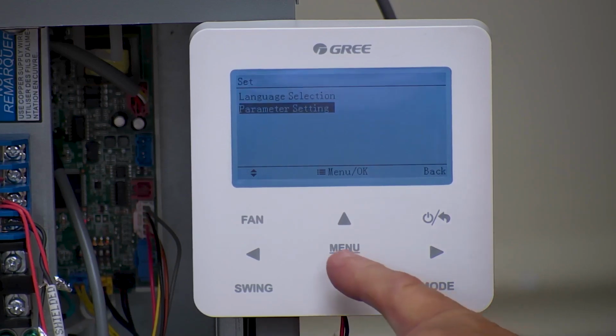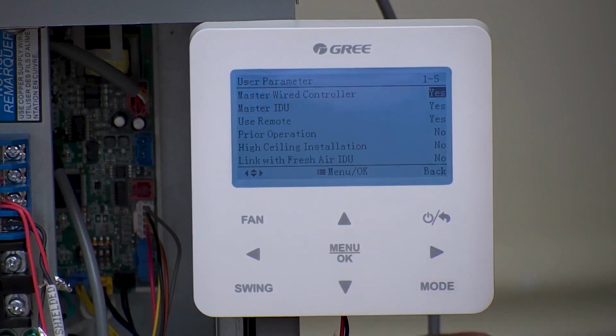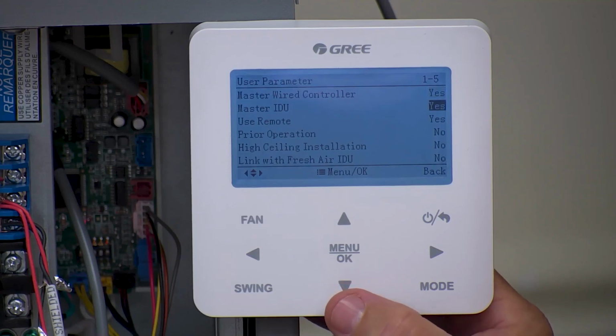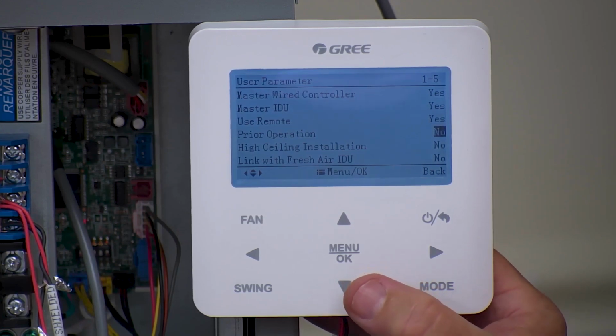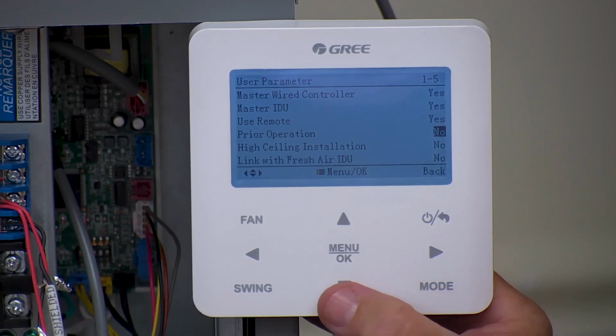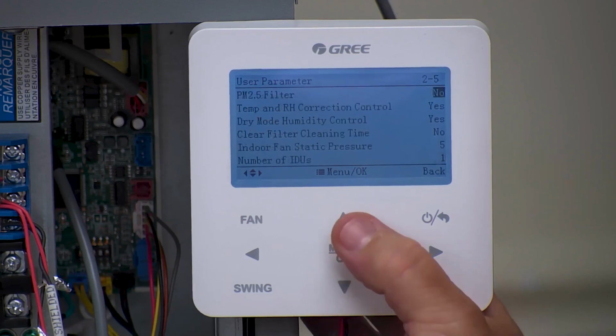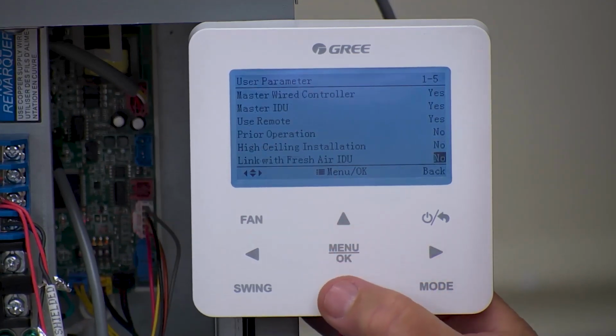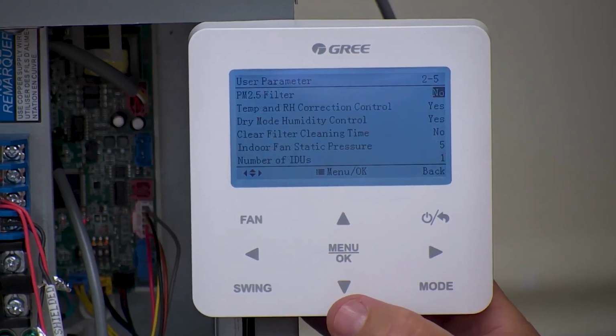And then the parameter settings. So this is set up as master wired controller, master indoor unit, use remote, which means you can set this thing up where you can still use the remote along with the wired controller, or you can say, no, I don't want the remote to be able to function. Prior operation, I wouldn't worry about that so much. High ceiling installation is not really going to apply to an air handler. Link to fresh air, that's only for a fresh air kit.